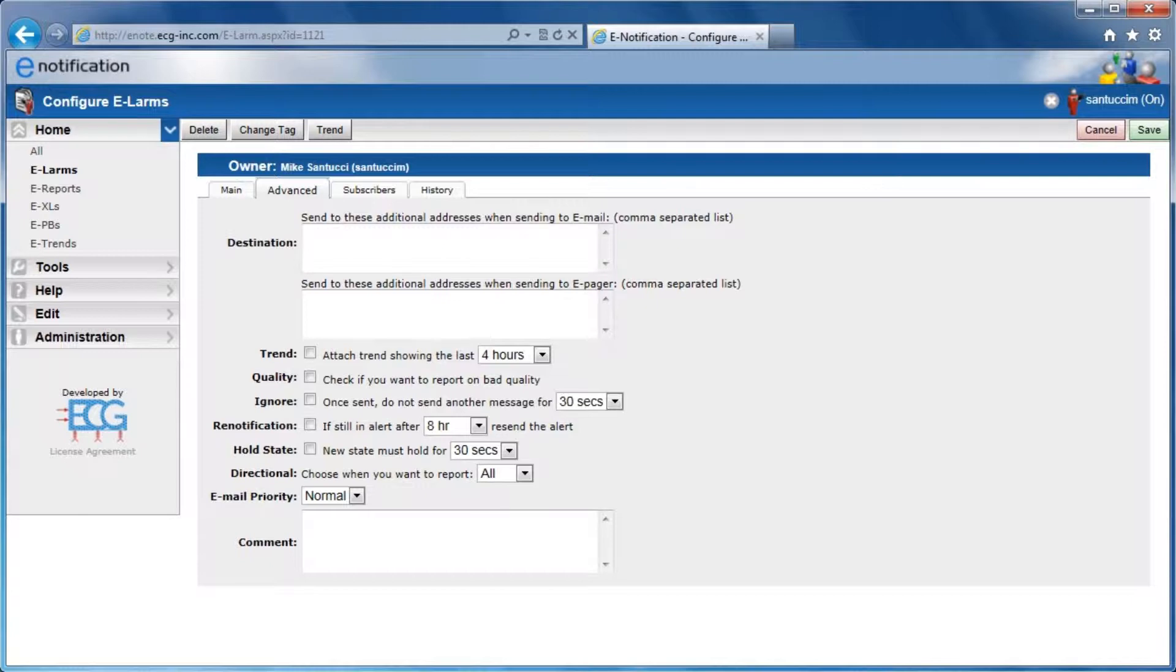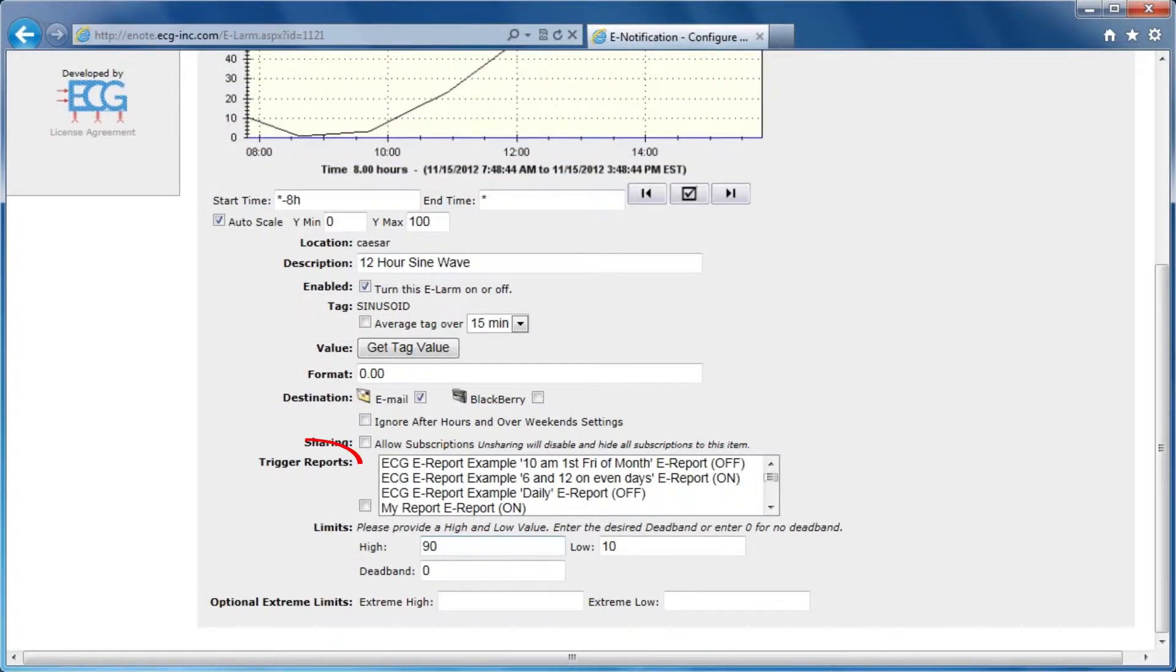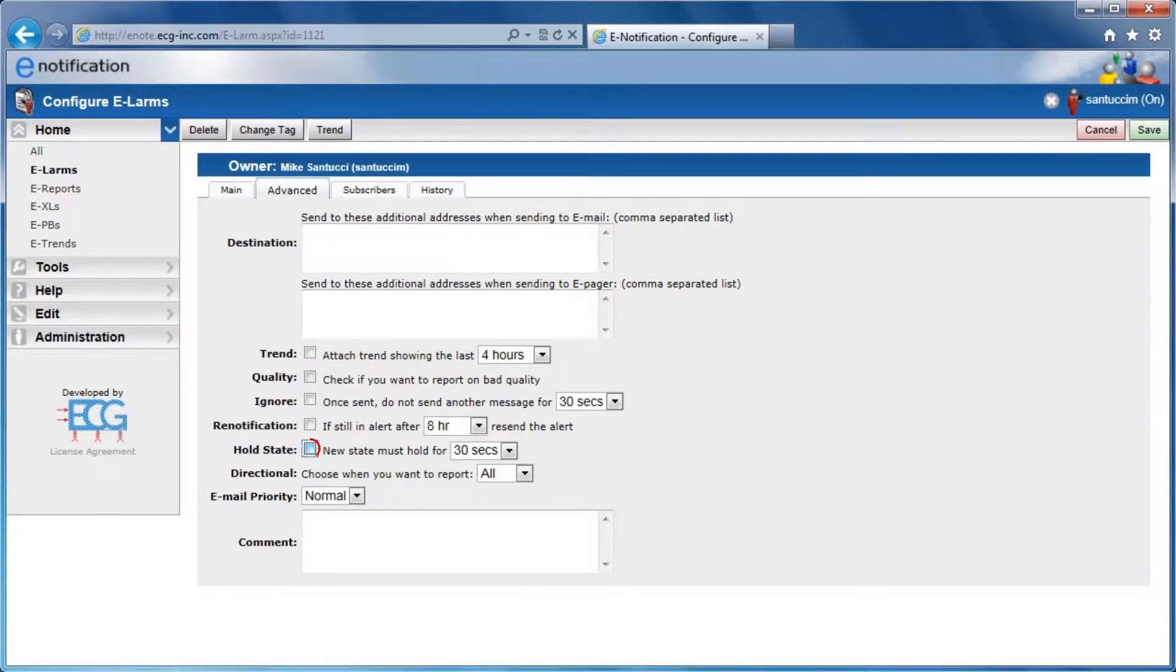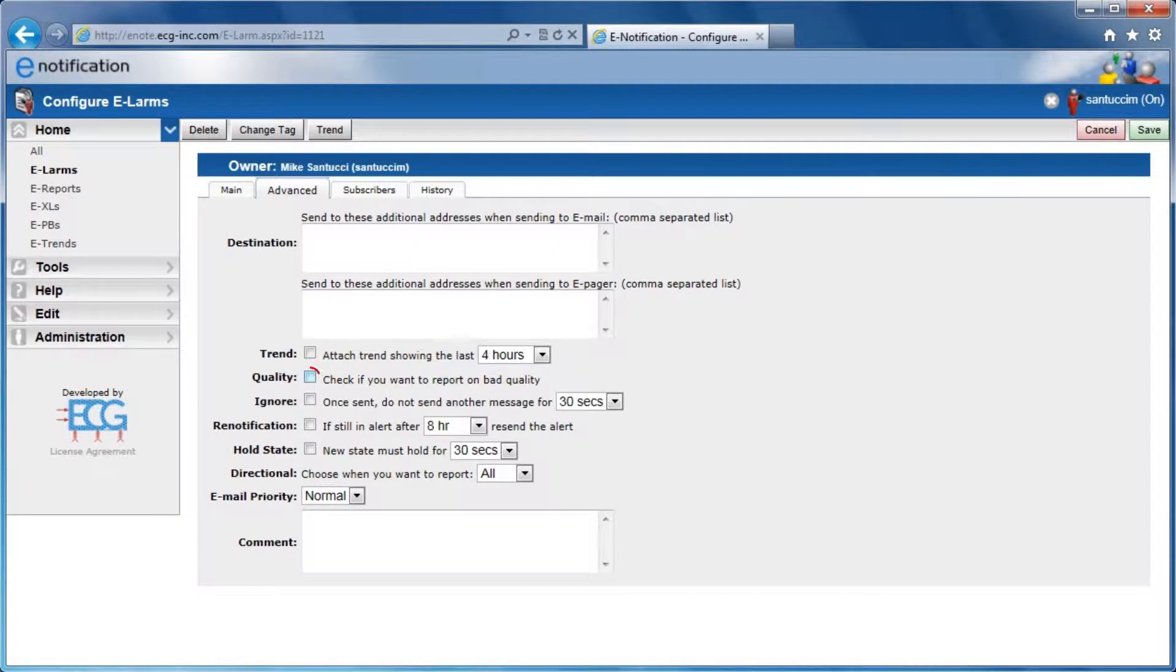E-LARMS can also be used to trigger the delivery of any predefined e-reports, e-XLs, or e-PBs. E-Notification can handle noisy signals from your system by averaging and holding tag values and preventing nuisance alerts. Select the Quality option to be alerted should a Pi Tag go offline.